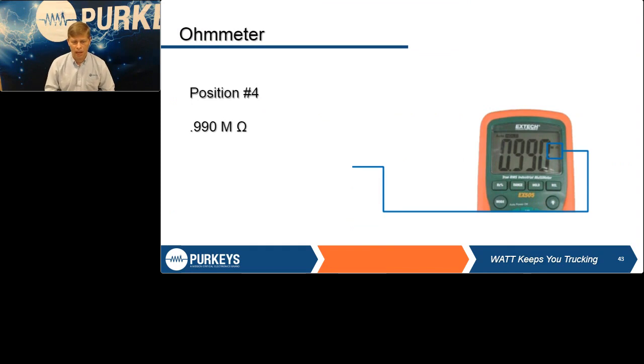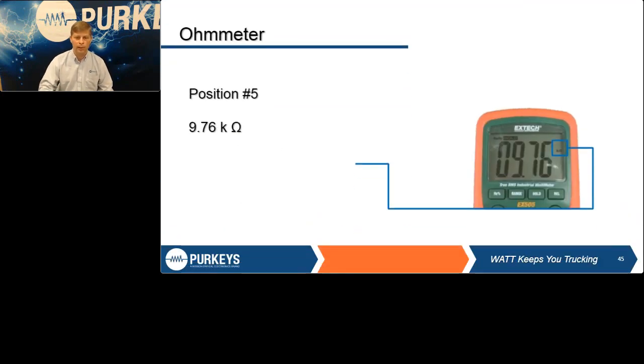This trips people up a lot of times. We have a 0.990 M. So quick glance, you've got the M, so you know you're on the mega scale, or million scale. 0.9 says you're just under 1 million ohms. Now, if y'all ever read at a tech event and go through one of my stations, I am a stickler on this. If you don't write it all the way out, how do I know you understand what that meter said? So if you do any station that requires writing something like this, make sure you write it all the way out, make sure you convey that you understand what that meter's telling you.